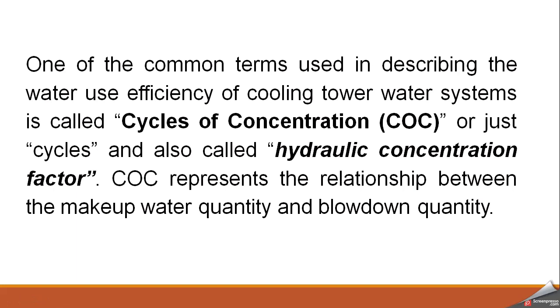It is normally called cycle of concentration, abbreviated as COC, or sometimes just cycle, and also called hydraulic concentration factor. So COC basically represents the relationship between the makeup water which we provide to the cooling tower during its operation and the blow down quantity, that is, the water which we discard during the operation of the cooling tower.